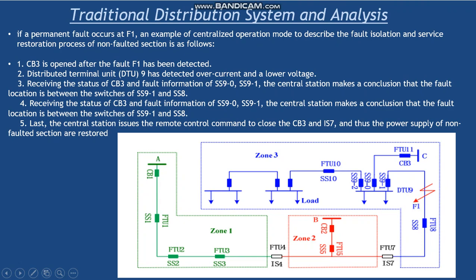First of all, circuit breaker 3 will be opened as soon as the fault will be detected. When the fault has been detected, the distributed terminal unit DTU9 will detect that there is an overcurrent and low voltage current. This information will be sent to the central station and it will conclude that the faulted section is in between switching segment 9-1 and switching segment 8. It will send a remote control command to close circuit breaker 3 and the switching interconnection switch IS7, and the power supply of non-faulted section will be restored.